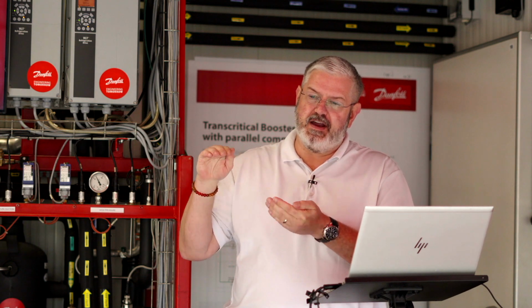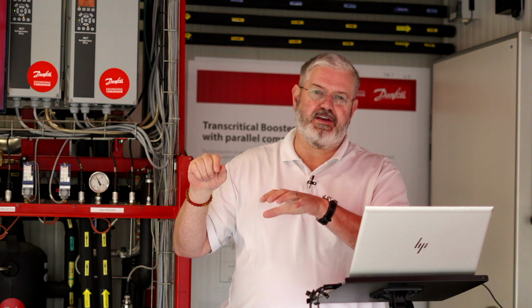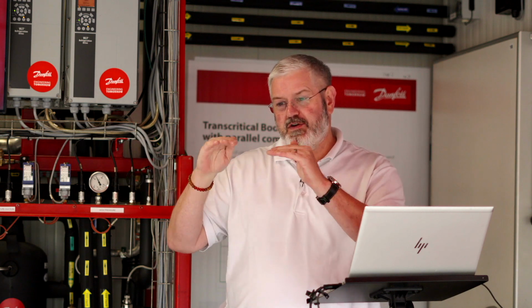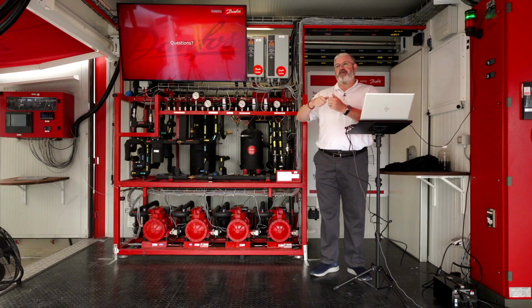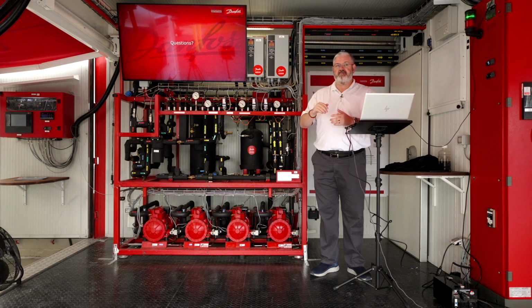So you're typically not going to have the high pressure valve doing its thing, with the gas cooler outlet temp and the COP line, in conjunction with the ejectors. You're going to have one or the other, but you can set it up to where you get below a certain ambient, you move to the high pressure valve. You get above that setting that kicked on the high pressure valve, you'll move back to ejectors so you can start working on the Venturi effect and the lift for medium temp suction gas return. And then if you have both defined in the pack controller, it will by default use the high pressure valve as a safety backup should something happen to the ejector solenoids.